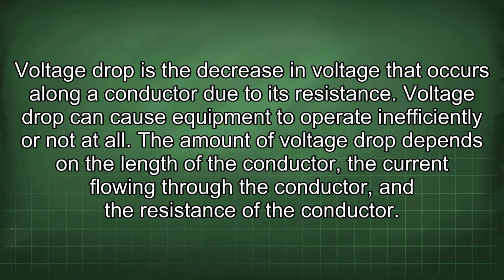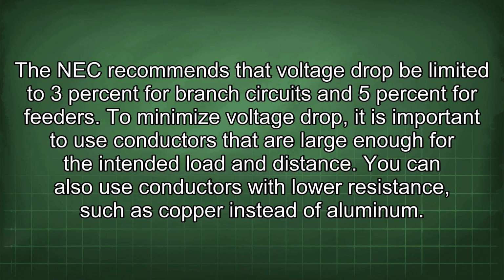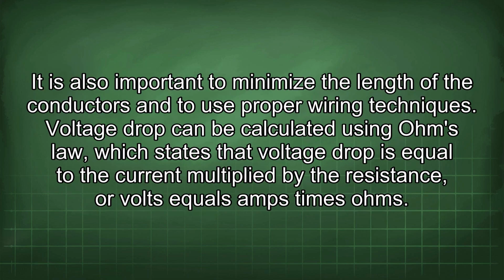Voltage drop is the decrease in voltage that occurs along a conductor due to its resistance. Voltage drop can cause equipment to operate inefficiently or not at all. The amount of voltage drop depends on the length of the conductor, the current flowing through the conductor, and the resistance of the conductor. The NEC recommends that voltage drop be limited to 3% for branch circuits and 5% for feeders. To minimize voltage drop, it is important to use conductors that are large enough for the intended load and distance. You can also use conductors with lower resistance, such as copper instead of aluminum. It is also important to minimize the length of the conductors and to use proper wiring techniques.